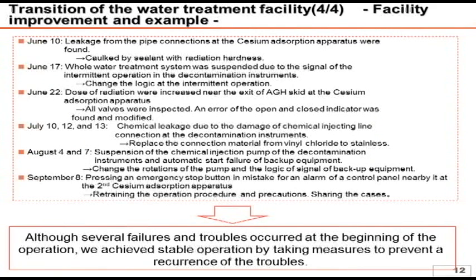In Kurion, there was leaking at the connection of the piping and the rupture disc. In Areva, the whole water treatment system was shut down due to the signal of intermittent operations. Also, chemical leakage at the chemical injecting line happened several times. We now believe that we have overcome these troubles and have achieved stable operations, achieved over half a year after we recognized the necessity of the water treatment facility after the earthquake in March.